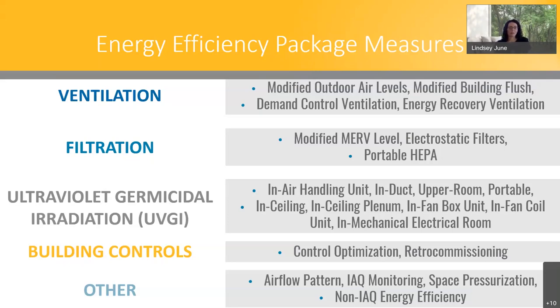IAQ monitoring: there are a few monitoring devices that can detect SARS-CoV-2 and other infectious diseases, but they're expensive. So the most common products available in the market track contaminants that can at best serve as proxies for infectious disease. They detect things such as PM2.5, which is the particulate size that causes significant health concerns in humans when inhaled. CO2, which is the byproduct of human breathing and an indicator of fresh air levels in a space. Humidity, within that range of 40 to 60%, is the range where the human bronchial system performs the best and infectious disease are most susceptible to damage.